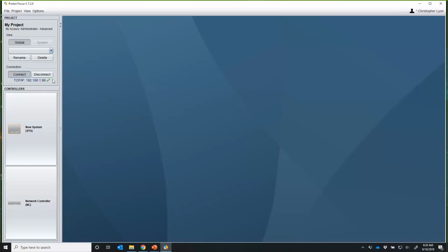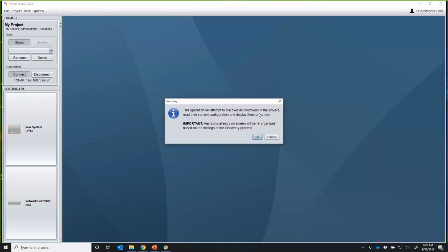But now that I'm connected, I just go to Options, Synchronize, and Discovery. Okay. One thing to note is if you have any controllers out here, if you've already brought some of them in, everything will be deleted. We are going to completely wipe the entire project you have open. So maybe you want to do this in a fresh, clean project. Because once we tell it okay, it's going to wipe everything out.